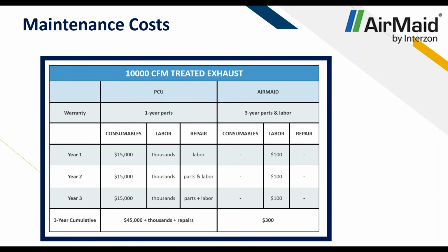So with that, I want to look at some examples here of PCUs versus AirMaids. AirMaid is a great solution. The one thing to mention though, before I get into this, is AirMaid cannot be used for solid fuel. So with solid fuel, you're pretty much going to have to go with the PCU no matter what. We do not want to use this with solid fuel. Something with the ozone and embers that can enter into the ductwork, we don't want them to interact at all.